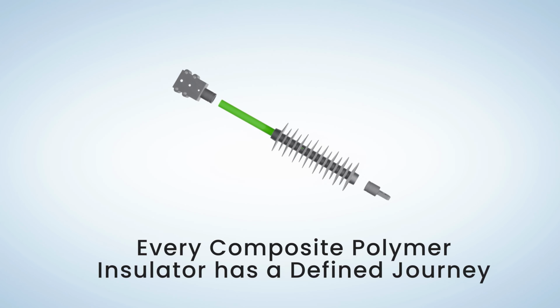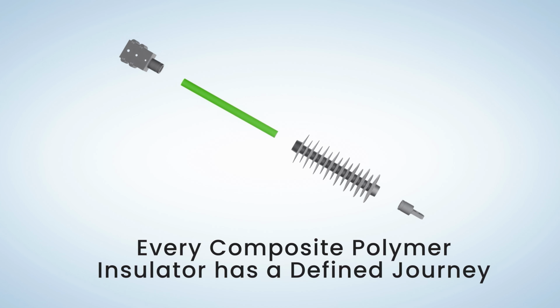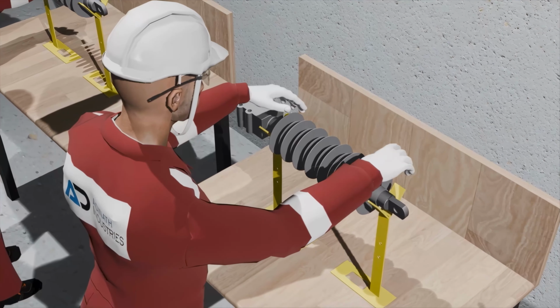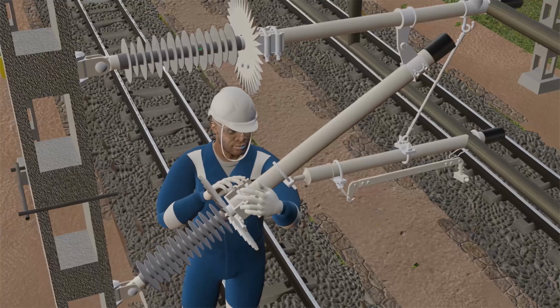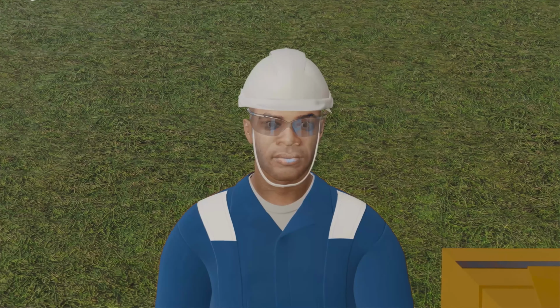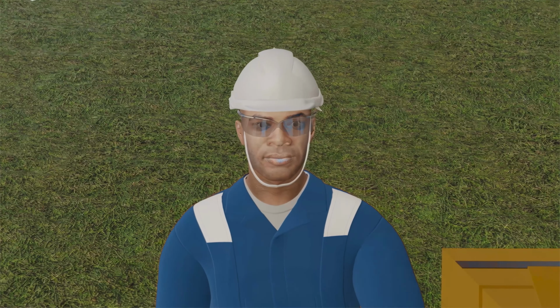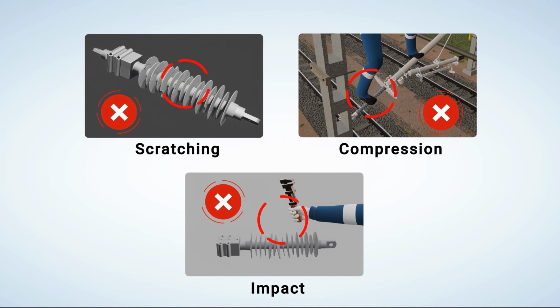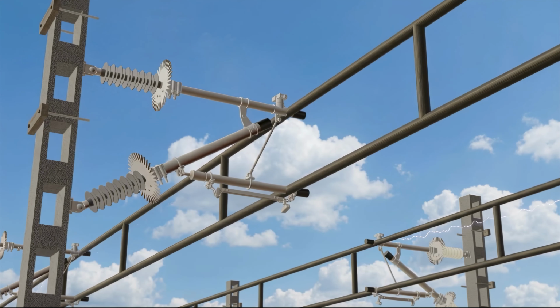Every composite polymer insulator has a defined journey. At every stage, from the factory to final energization, its performance depends on how it is handled. During installation of the polymer insulators and assembly of the cantilever, stepping or standing on the insulators is strictly prohibited. Any scratching, compression, impact, or surface damage during installation must be avoided, as it can lead to premature failure during service.